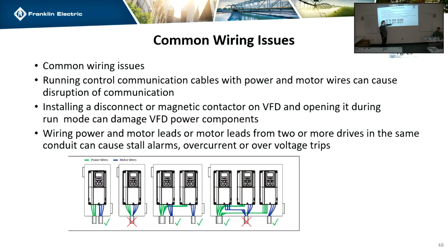You can wire all of the incoming power to multiple drives through one conduit. It's fine. It's not going to cause any problems. It's when you start combining the outputs that you have a problem. So in this one they're showing 2, but this could be 3, 4, 5. You could have all your inputs coming through one and split off, but then each output needs to have its own conduit because that's what's going to mess the signals up.